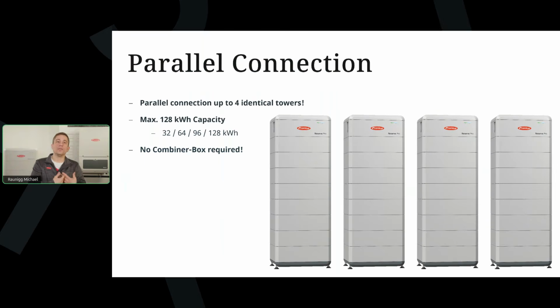Always only combine the same number of modules, don't mix them. You can install, for example, 2 towers, 3 towers, or even up to 4 towers to each other, depending on your capacity needs. So with 2 towers in parallel, you can achieve up to 64 kilowatt hours. With the 3 tower variant, 96 kilowatt hours, and with the 4 tower variant, a maximum capacity of 128 kilowatt hours.